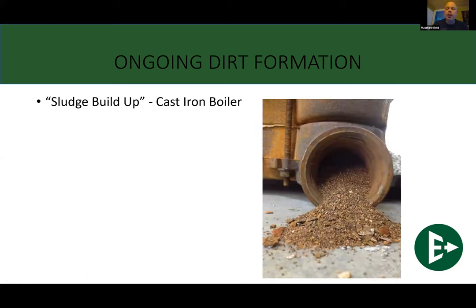Sludge build up inside of these boilers. As we oxidize and we get that sludge build up, which essentially is just ferrous metal iron particles floating around inside of a system, that's what will lead to this style buildup. Now, the old cast iron systems that we used to use and still do use in some applications, I get the comment all the time: well, those things never had any scale buildup inside of them. They ran for 20 years. Which is true. They did.